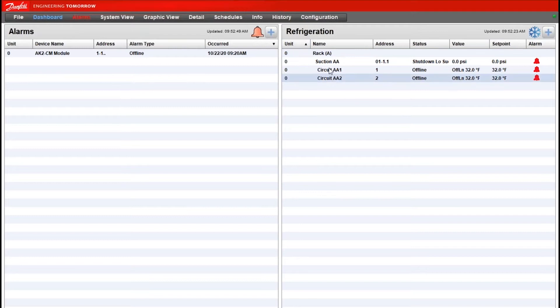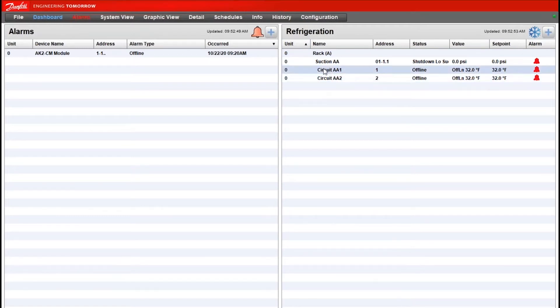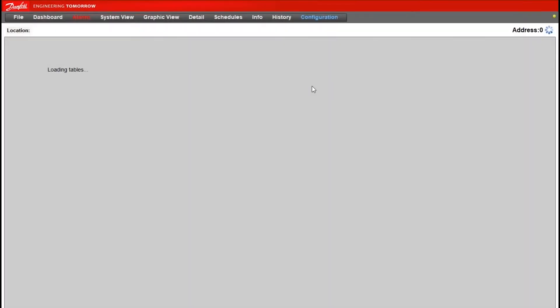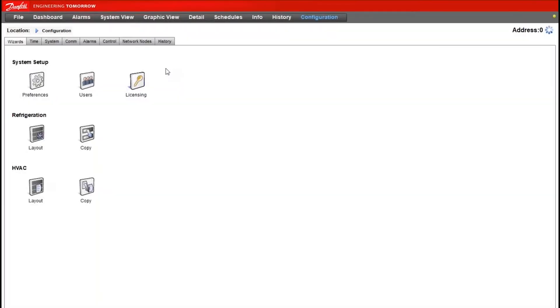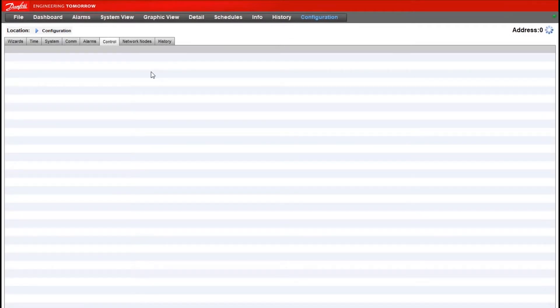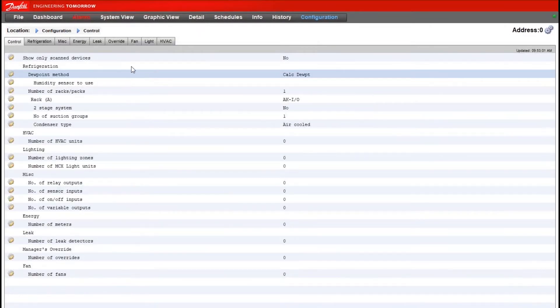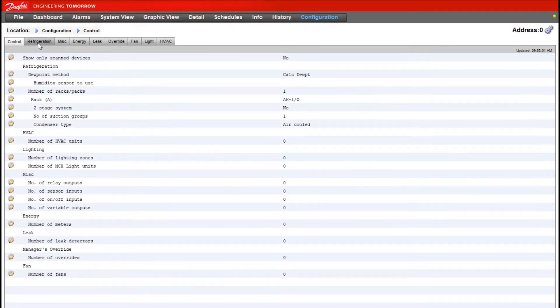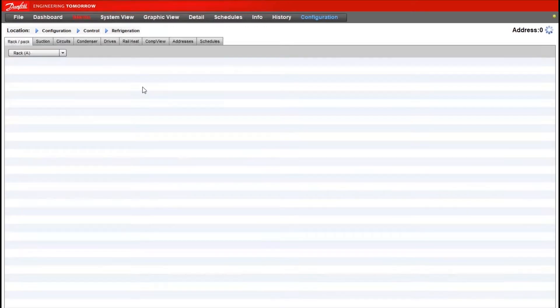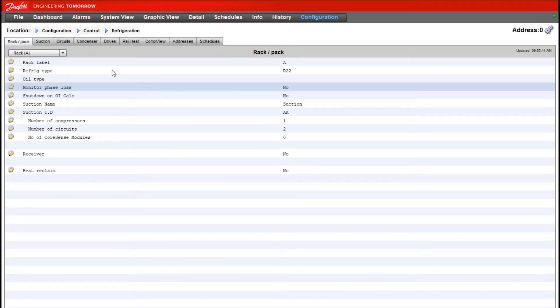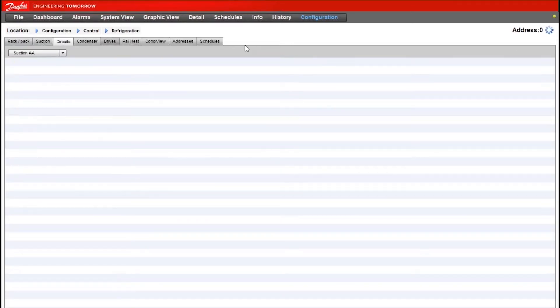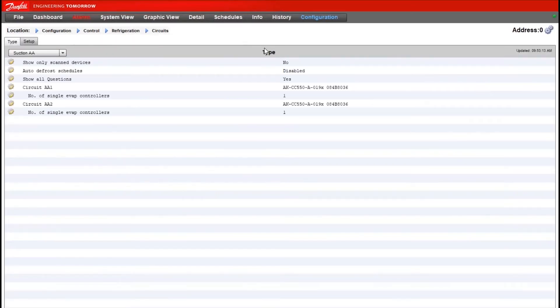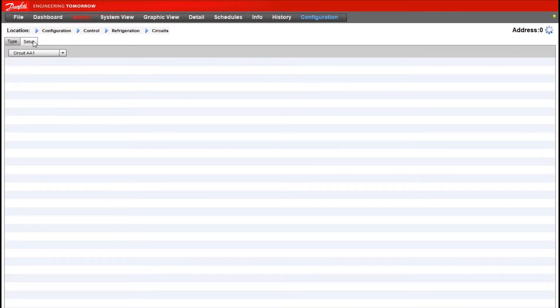In this video I have two case controllers configured, one and two. The first step in the process is to make sure we're bringing in the data points or importing the data points that we want to use in the logic. I will go to configuration, control, refrigeration, and then circuits. We're under the assumption that the case controllers are already configured in system manager.